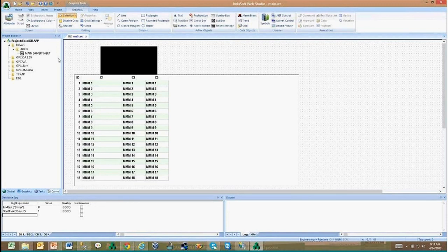Now, the most recent version of the ABCIP available to download from the InduSoft website supports a new mode which does not use tag names to communicate. You can configure the ABCIP driver to use index IDs to communicate with the PLCs.